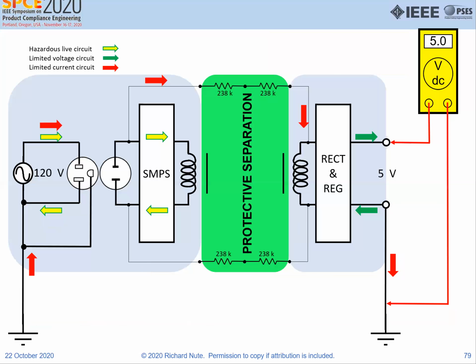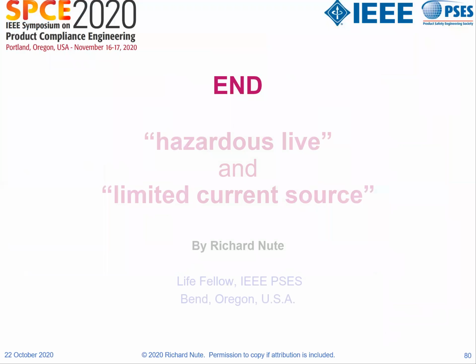Finally, if this thing is grounded through other equipment, all the limited current passes this way, and we still have 5 volts DC. You have no voltage to the ground. So the voltage is low, no electric shock effect regardless of current. And that's it. That's the end of hazardous live and limited current source. The limited current source is the equivalent of a limited voltage source.